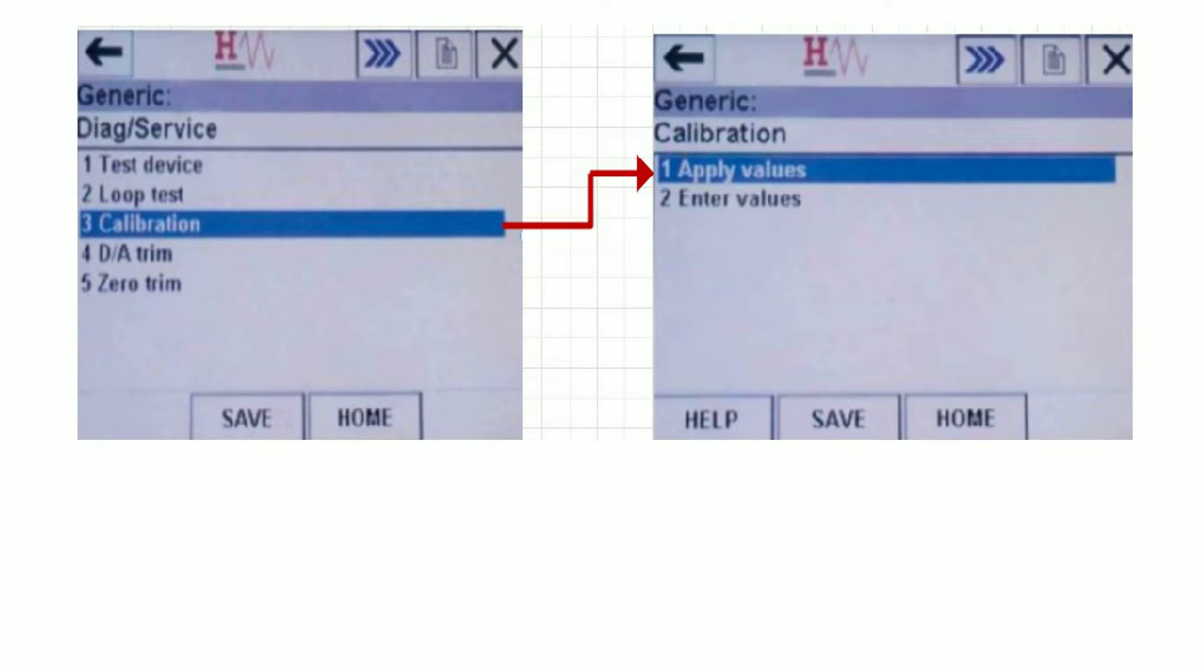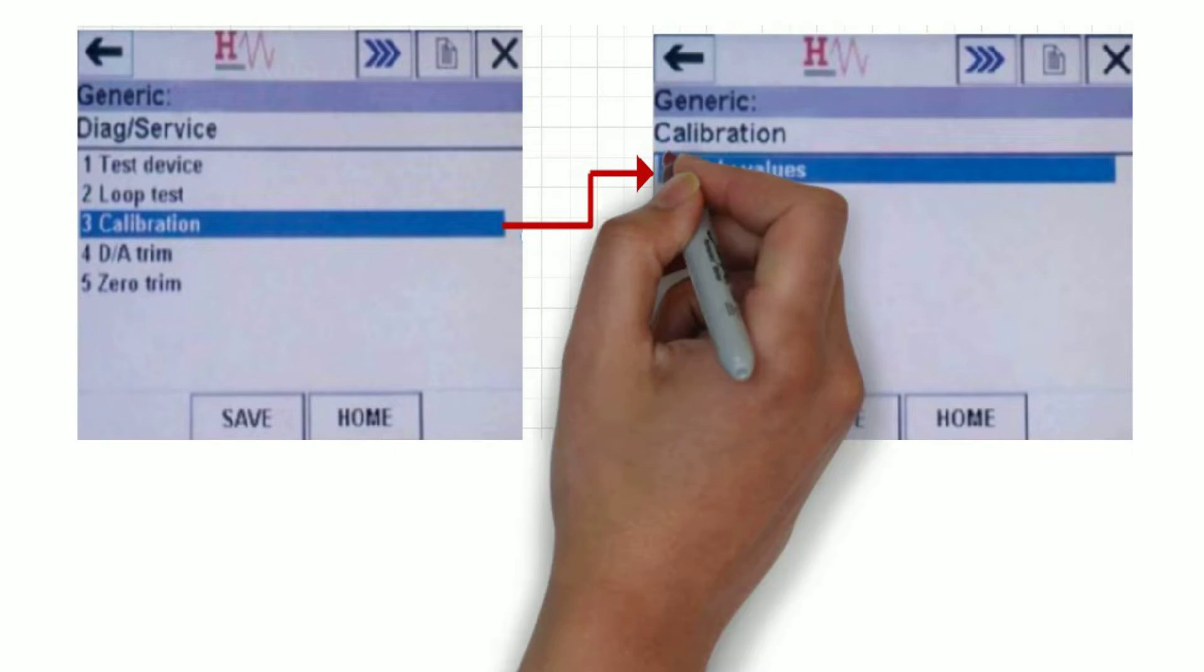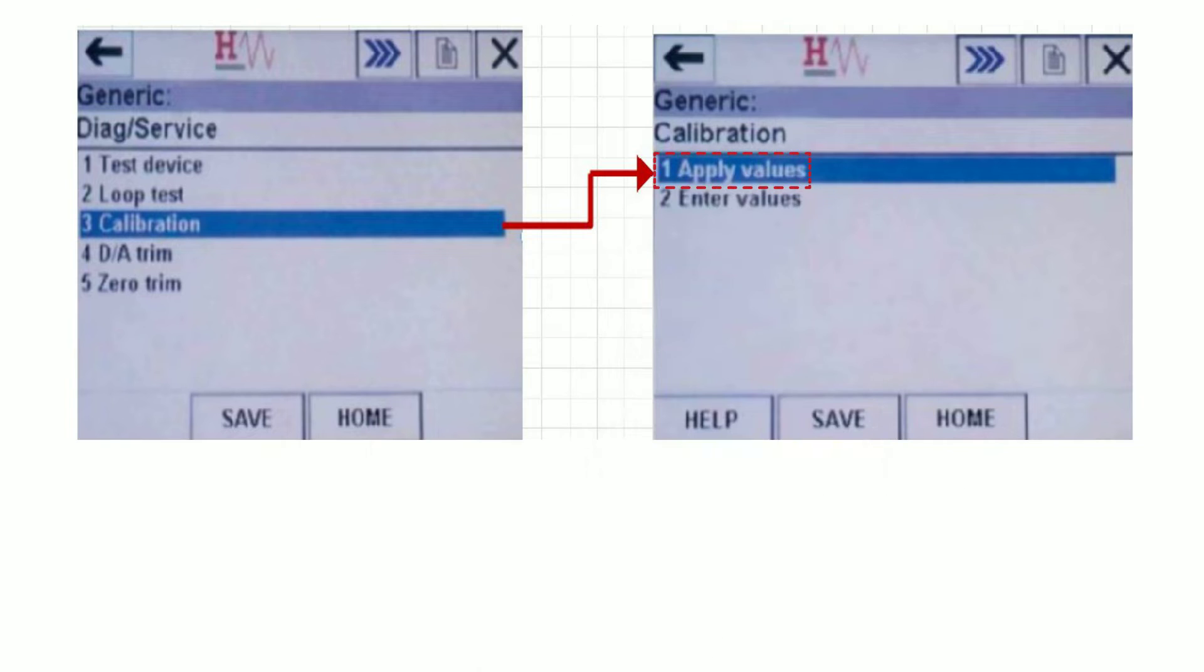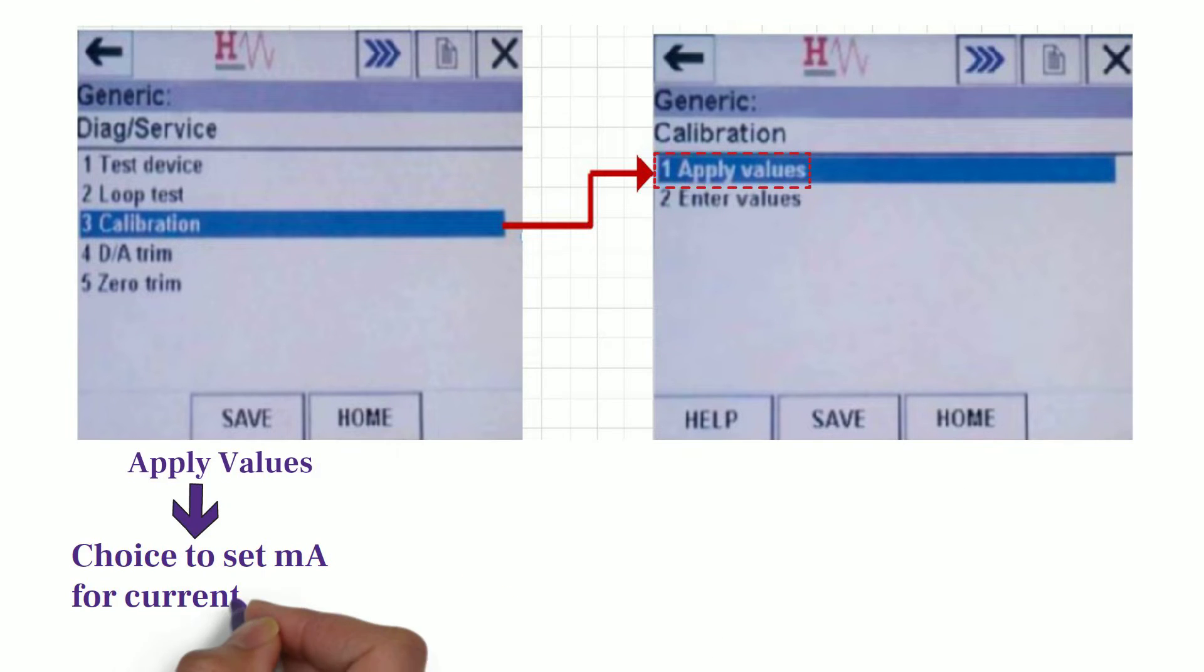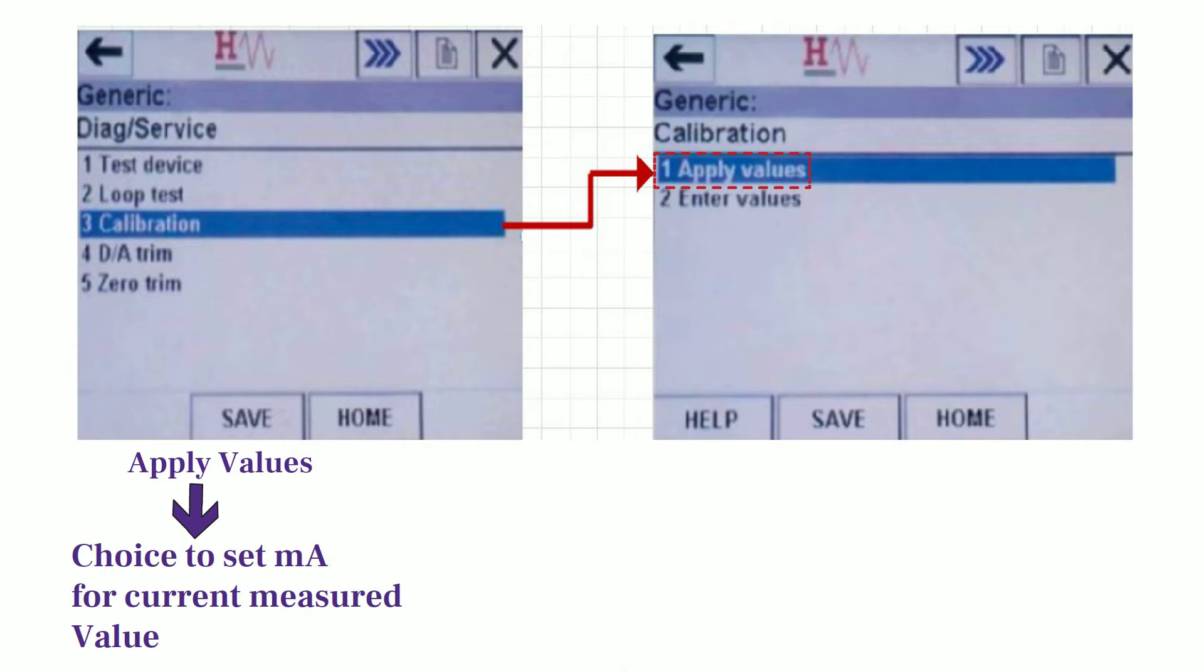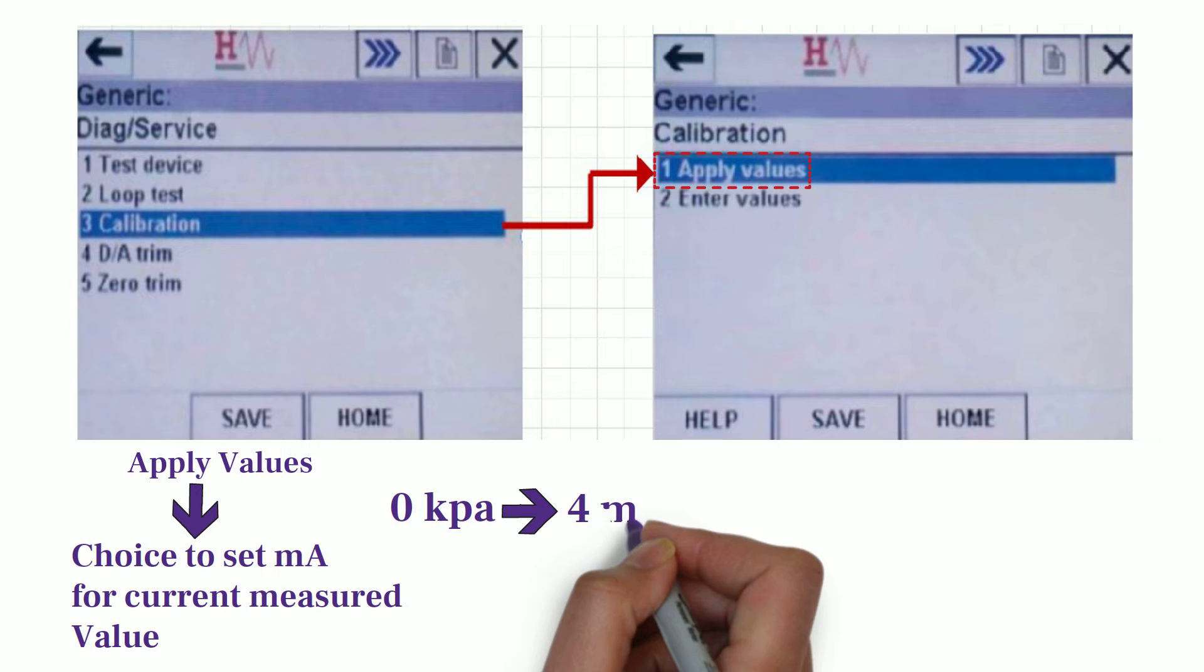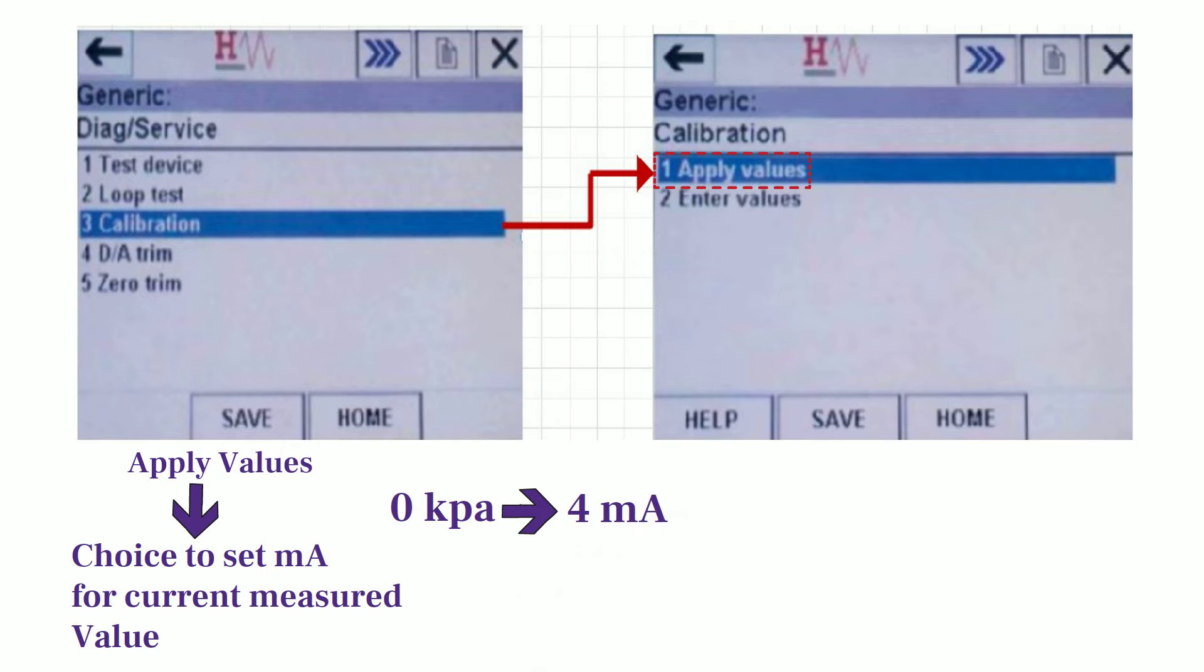Calibration Menu gives you two options. First option is Apply Values. This option gives you the choice to set the milliampere value for current measured value. For example, if the current measured value is 0 kPa and you want to set as 4 milliampere for this range, then you need to select Apply Value option.